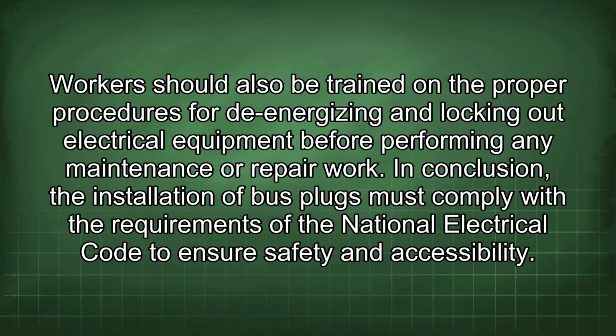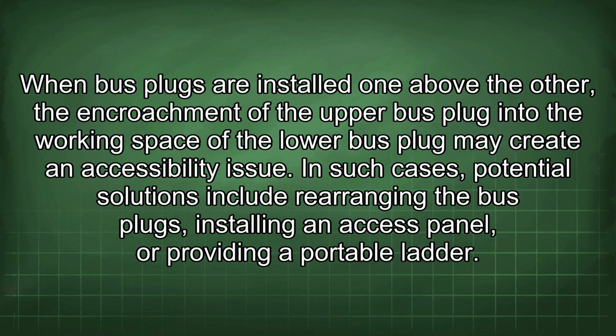In conclusion, the installation of bus plugs must comply with the requirements of the National Electrical Code to ensure safety and accessibility. When bus plugs are installed one above the other, the encroachment of the upper bus plug into the working space of the lower bus plug may create an accessibility issue. In such cases, potential solutions include rearranging the bus plugs, installing an access panel, or providing a portable ladder.